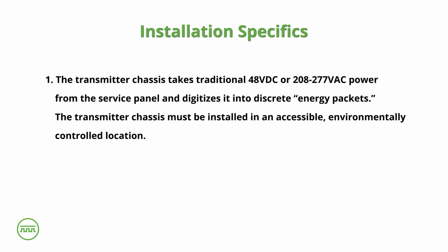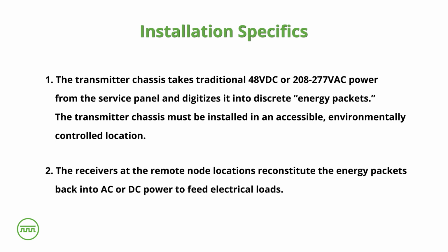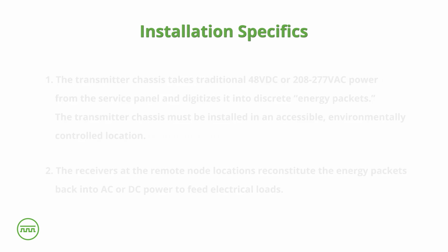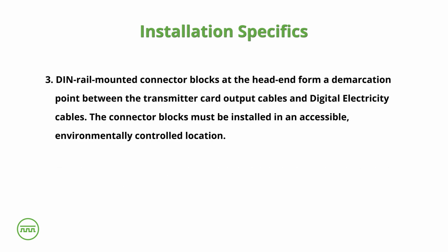The transmitter chassis takes traditional 48 volts DC or 208 to 277 volts AC power from the service panel and digitizes it into discrete energy packets. The transmitter chassis must be installed in an accessible, environmentally controlled location. The receivers at the remote node locations reconstitute the energy packets back into AC or DC power to feed electrical loads. DIN rail mounted connector blocks at the head end form a demarcation point between the transmitter card output cables and digital electricity cables. The connector blocks must be installed in an accessible, environmentally controlled location.